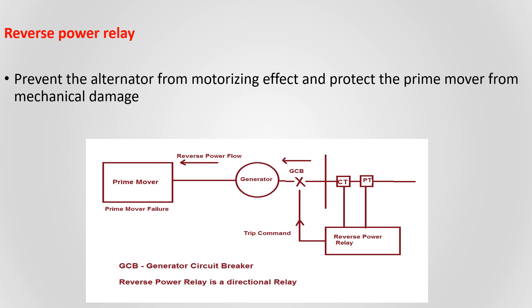If you see the diagram here, during normal power flow the generator has to deliver power to the MSB. Inside the MSB a busbar is there, and another generator is also connected to this busbar. When reverse power flow occurs, the faulty generator takes power from the busbar. So if you have the relay, when reverse power flows it gets energized and gives a tripping signal to the ACB to open the breaker. In this way we can protect the prime mover and generator.